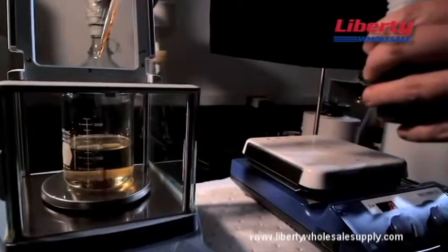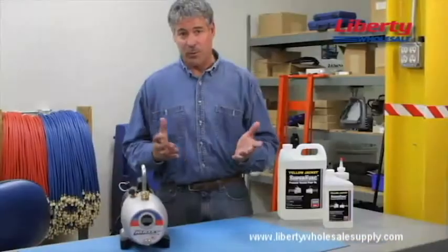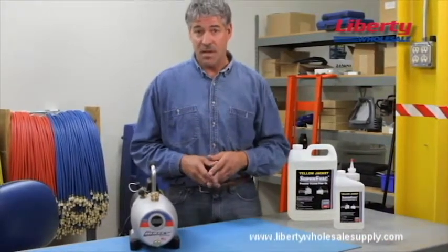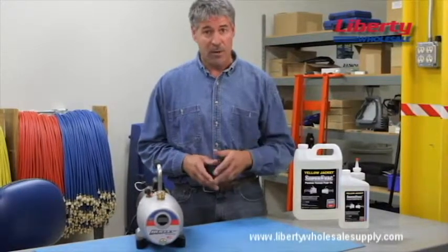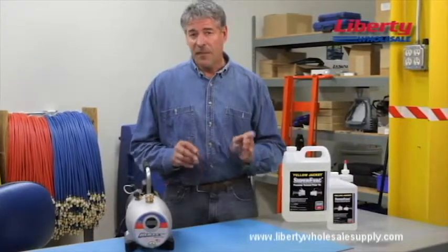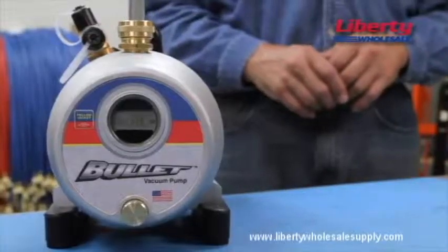together with a high boiling point and oxidation stability level. In other words, it enables the pump to pull a much deeper vacuum than most other vacuum pump oils, while lubricating your pump and absorbing contaminants, including moisture. This means your pump will perform better and more efficiently even after the pump gets hot.